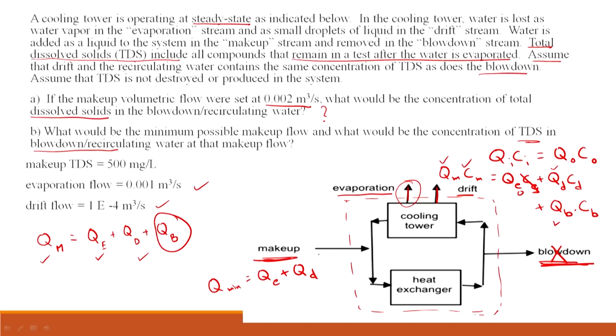Think of this: you have water at a certain TDS coming in, and over time you have loss of water. But is the water loss via water vapor going to also remove TDS? No, it is not. So the TDS is building up inside the system. If you have no blow down from time to time, you would expect the TDS within the system to increase.